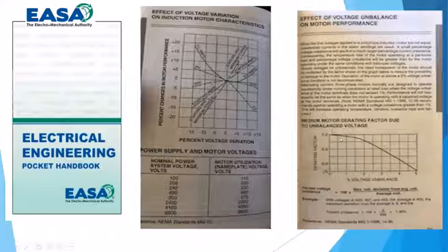And so you can see on the right hand side here that when it's balanced, maybe a 1% deviation, you don't have to derate the motor. But when you get out to 5% of voltage imbalance, you're supposed to be derating that motor by 25% in order to maintain its life. So that's where a lot of motor people get into trouble, because it looks good. The power is up to 460 volts, and the power company says, well, we balance you to plus or minus 10%. But it's the balance of those three waveforms.